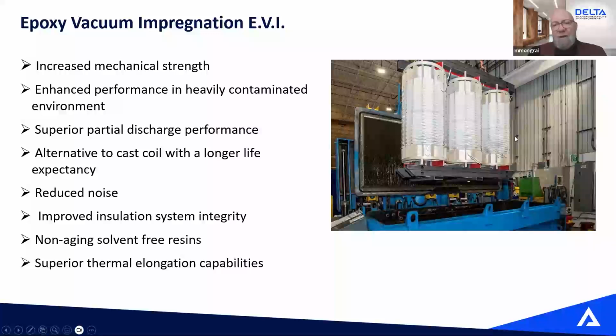It's also a better dielectric than varnish and polyester, and it's a very good moisture repellent. Varnish and polyester resin will act more like a sponge. It will attract and retain humidity. Epoxy will repel. And I always do this when we tour the plant. I go on the shop floor, I take a piece of epoxy coil and have this bottle of spray water, and you spray water on the windings, and it's like wax paper, the water is just repelled. So that's why we use epoxy at Delta for all of our products, because it's the best coating material: flexible, a better dielectric, and a better humidity repulsive material.